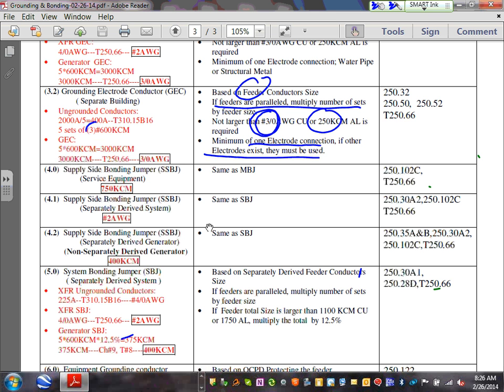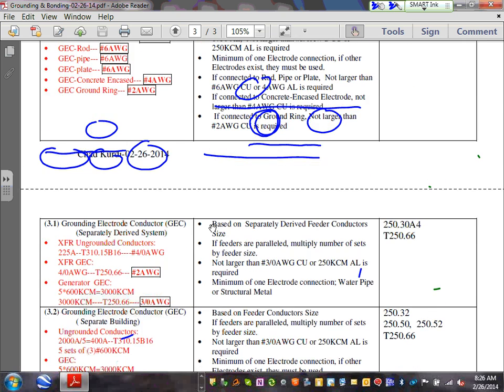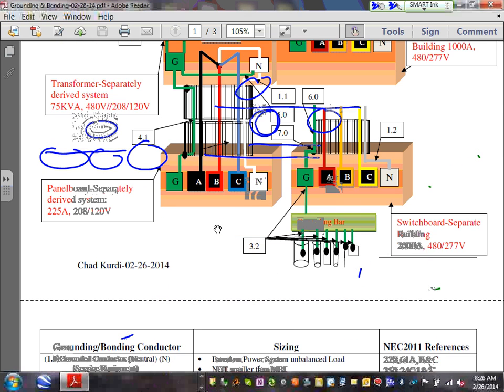So take this. We size the conductors like we did, and we do the calculation like we did. Then you take the 3000 kcmil to this table, and that will get you maximum, which is 3 aught. So at the second building, Karen, we also have to use a 3 aught to tie to the ground bar. Now tying to the ground rod, you don't have to go larger than number 6. Any comments, guys? Any questions about grounding and bonding at the second building?